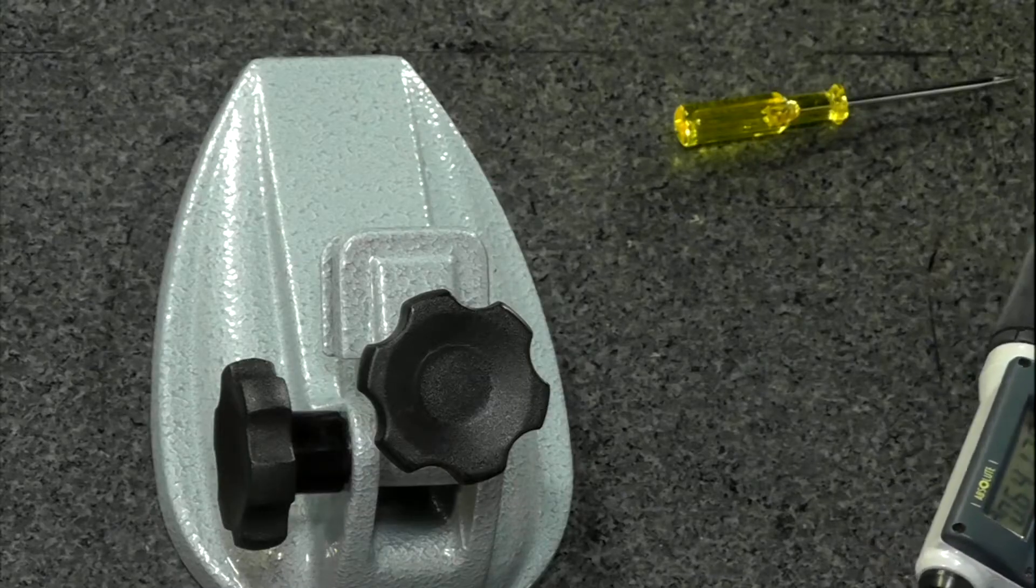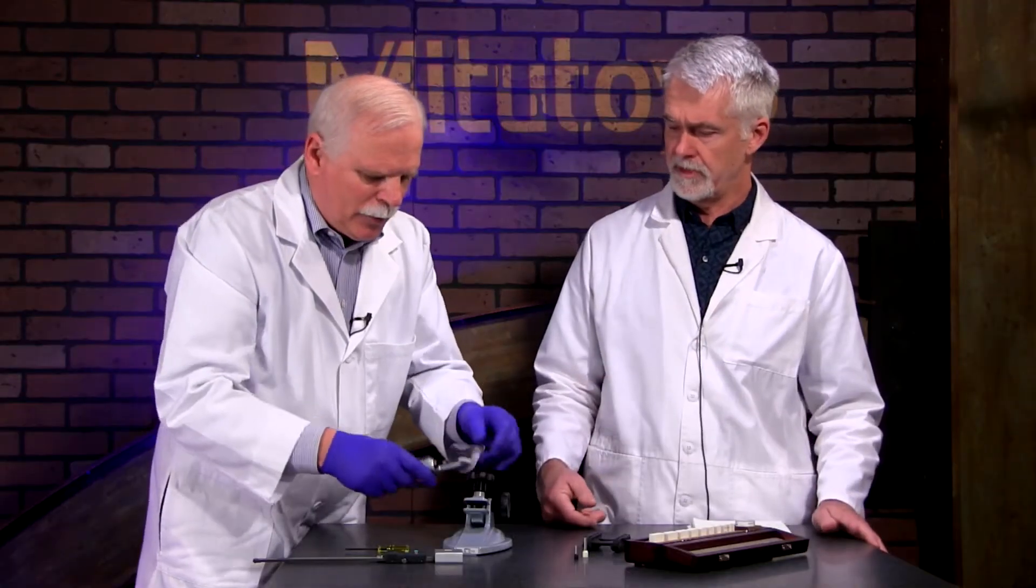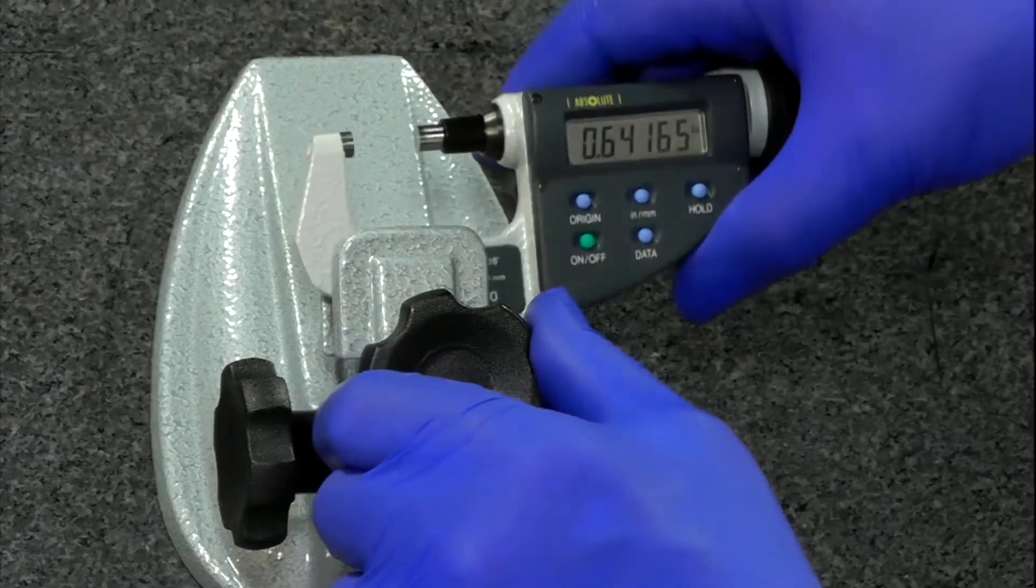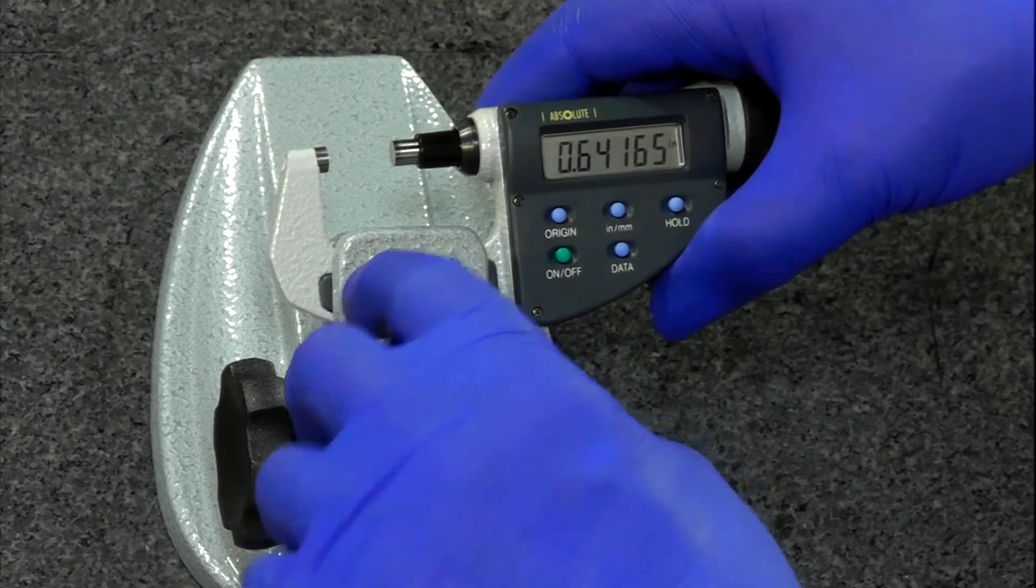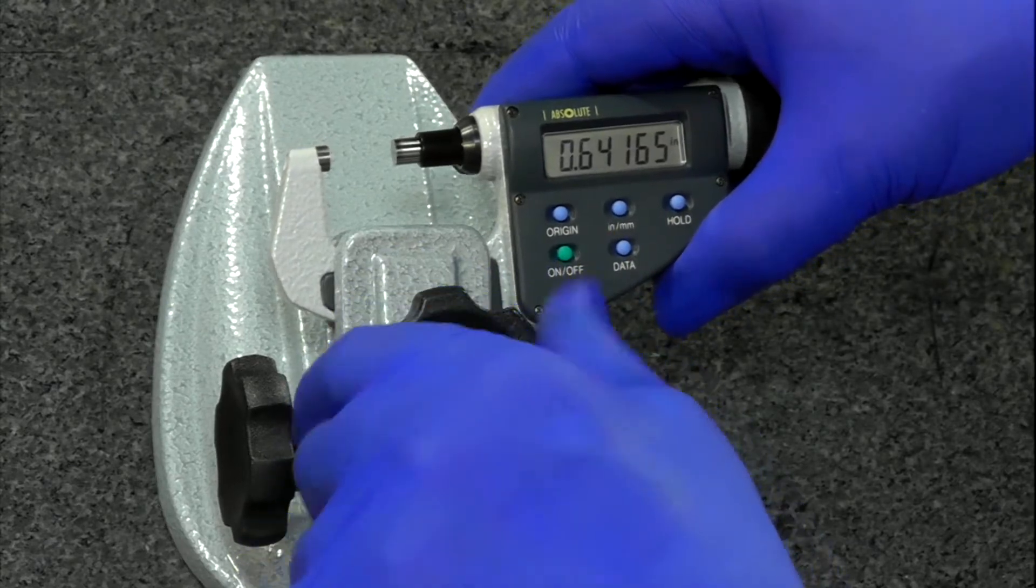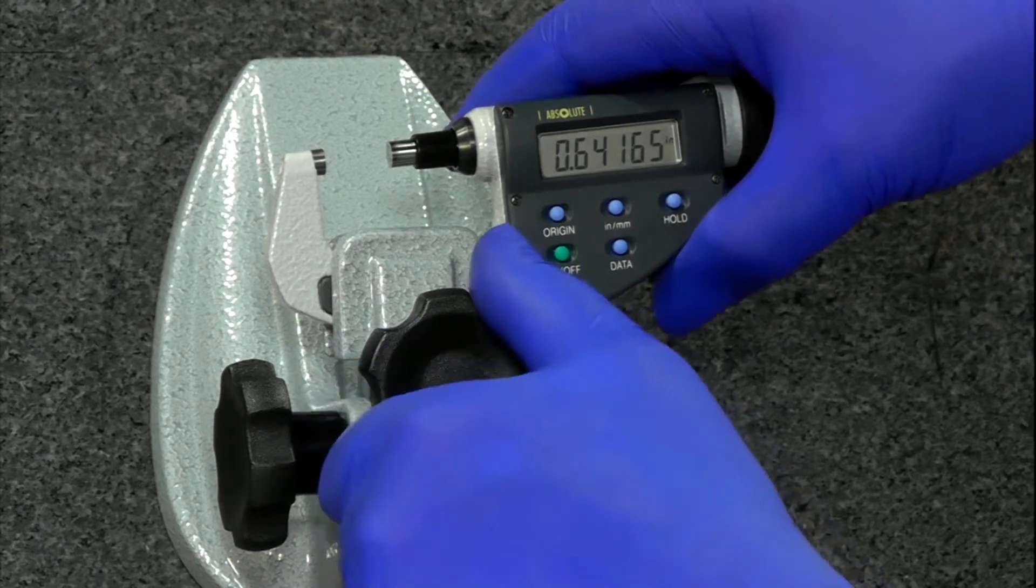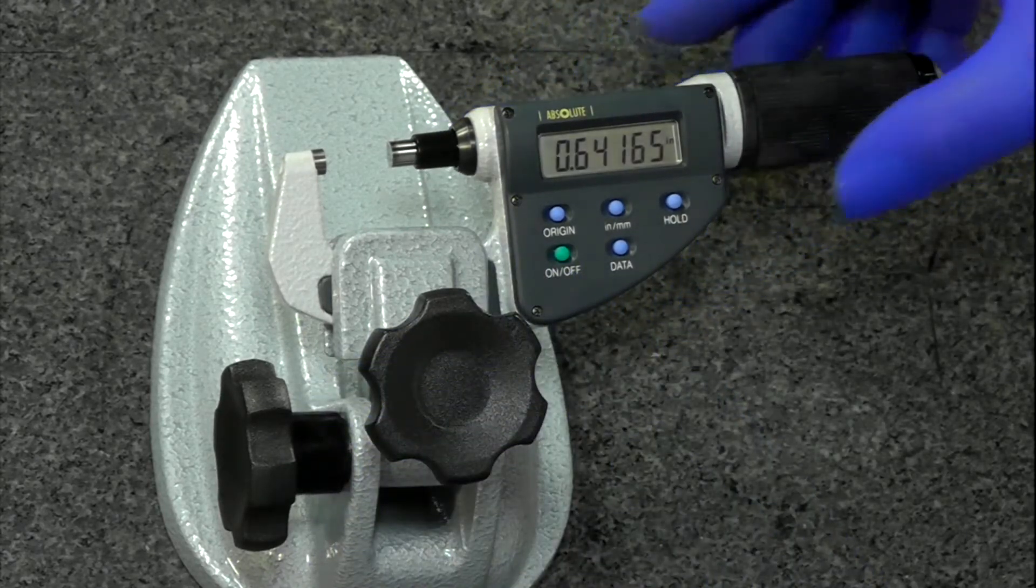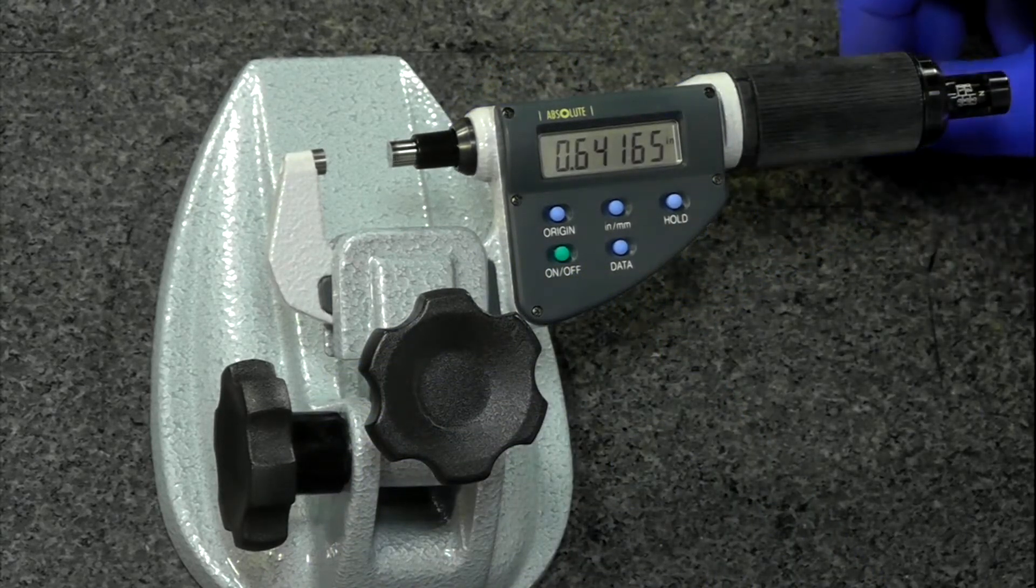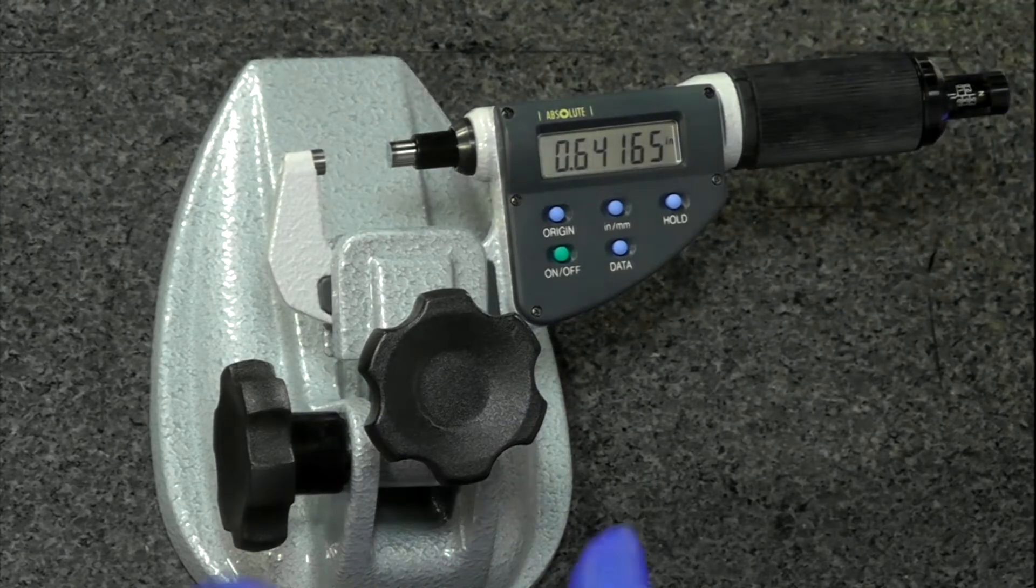What's the purpose of these low force instruments? For measuring some harder plastic, some rubber parts, things that would deform very easily with using just a normal handheld instrument. Everyone has a different feel, where this will give us very similar readings between people, between operators.